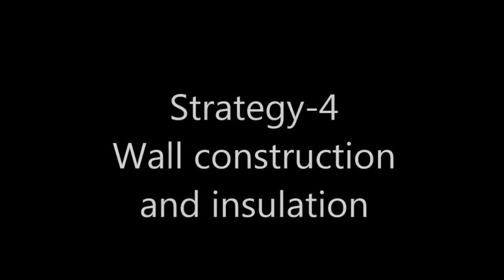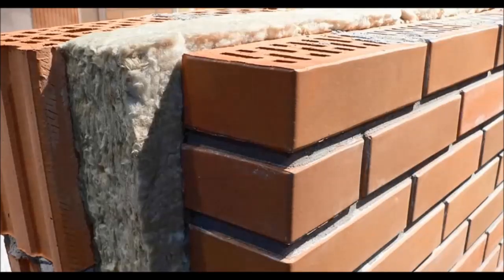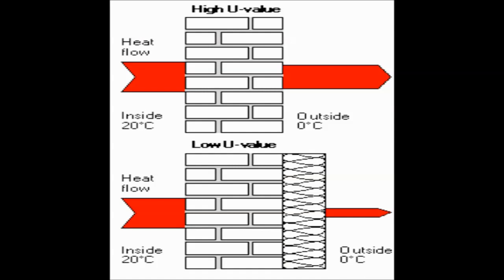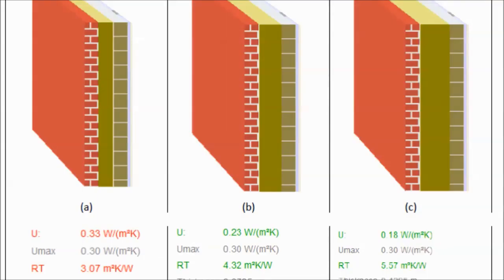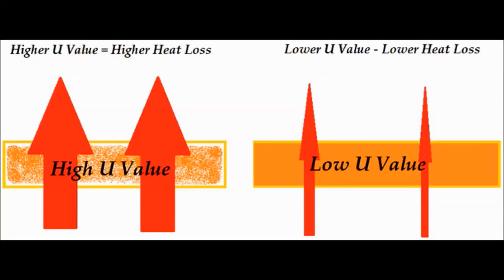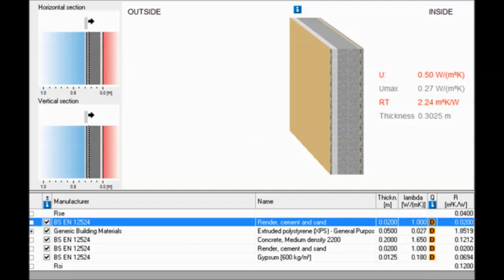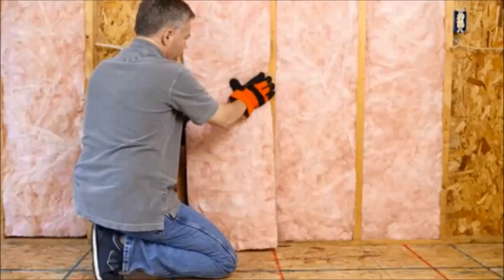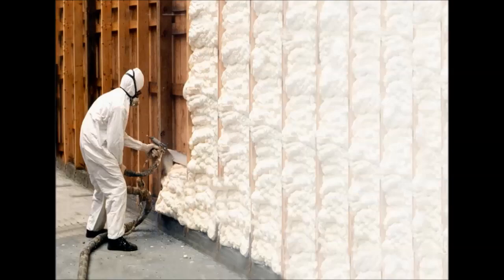External walls are the main boundaries between the inside of the building and the outside conditions. Hence, they mainly affect the heating and cooling of the building. The overall heat transfer coefficient, U value, is a measure of heat loss through building walls or floors. A high U value indicates a high heat loss through the wall or roof section, while a low U value indicates a low heat transfer. The building initial load calculation is utilizing a wall construction with a U value of 0.5 watts per square meter Kelvin. This value is good but can be better if the insulation thickness was increased.